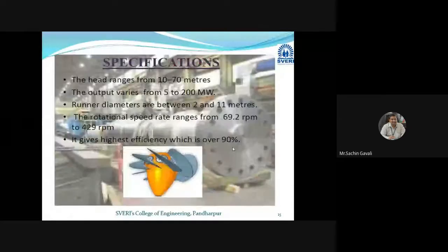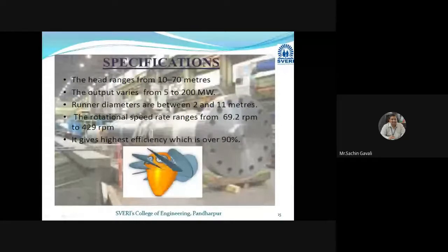So the specifications: the head range is generally 10 to 70 meters, though some books give different specifications for the range of low head. The output varies from 5 to 200 megawatt. Then runner diameters are between 2 and 11 meters.